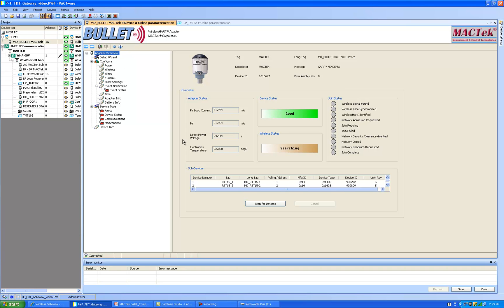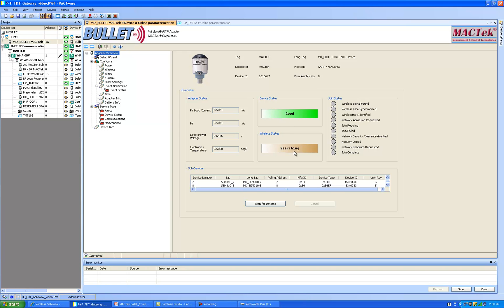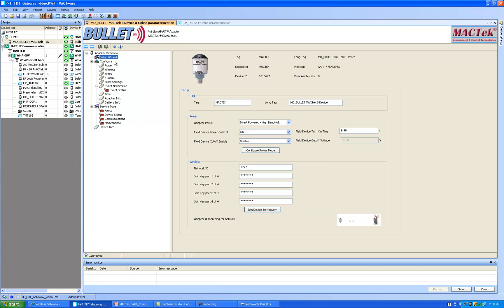On this page you can see the primary variables of the bullet, the eight devices that are attached to the bullet. You see them paging through and the general status. Basically, it says the bullet has no alerts or errors but it is searching for an adapter. The reason it's doing that is I have the network ID and join key set to an inappropriate value.